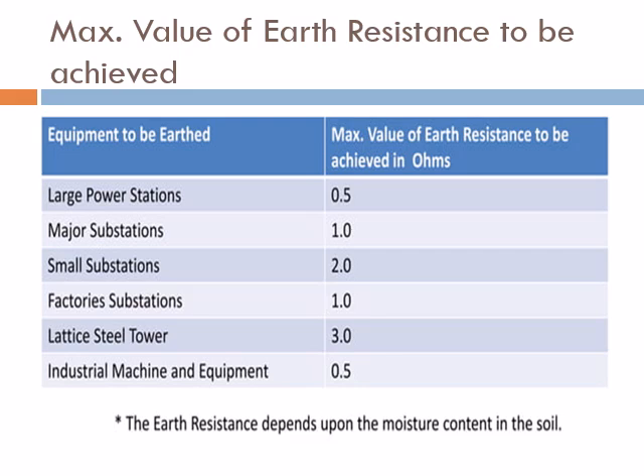Next is about the maximum value of earth resistance to be achieved for equipment, expressed in ohms. For large power stations, the maximum earth resistance is 0.5 ohms. For major substations, it is 1 ohm. For small substations, 2 ohms. For factory substations, 1 ohm. For lattice steel towers, 3 ohms. For industrial machines and equipment, 0.5 ohms.